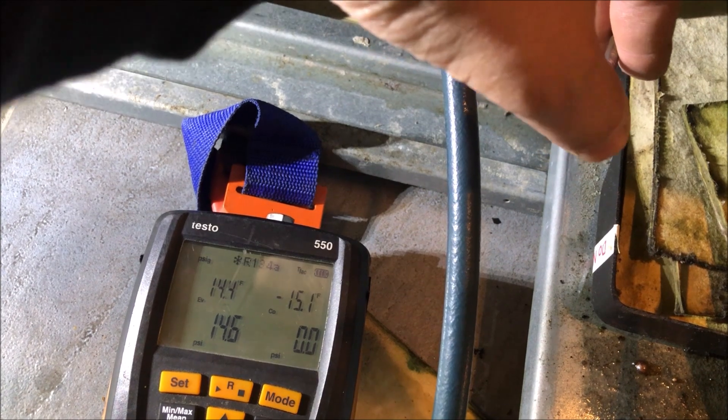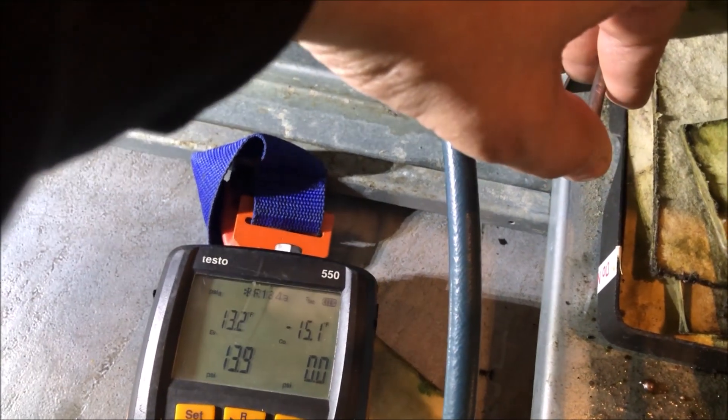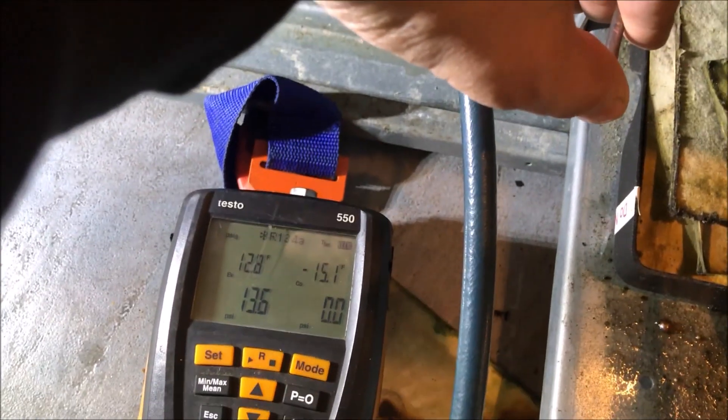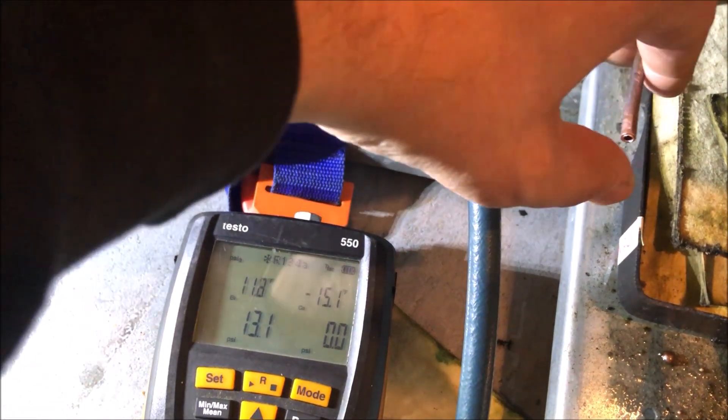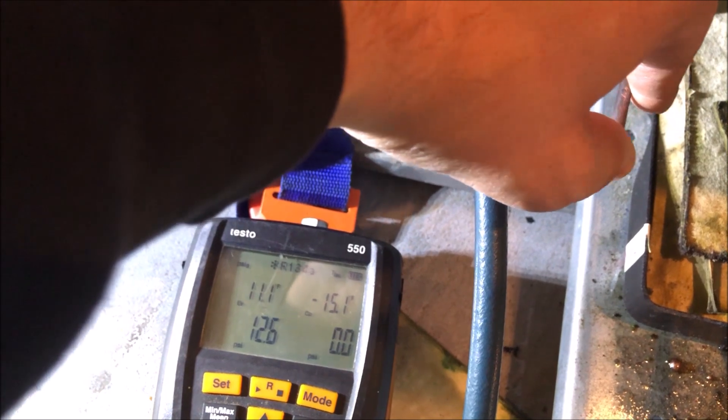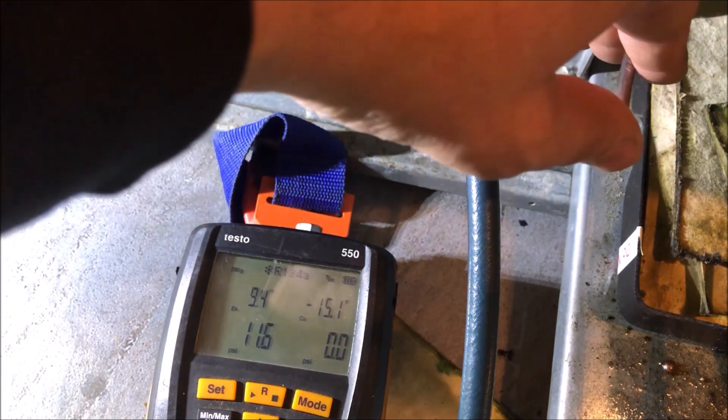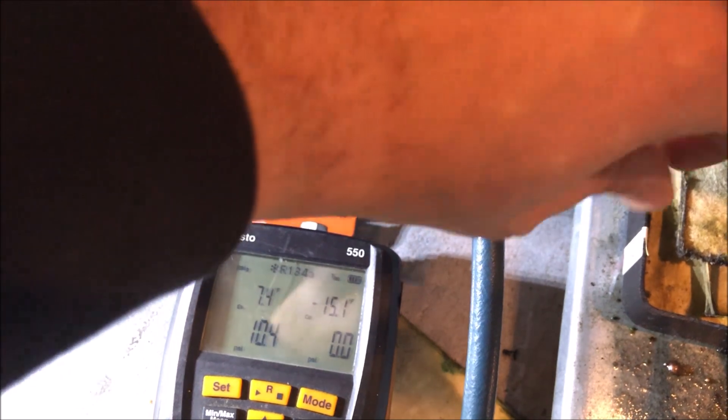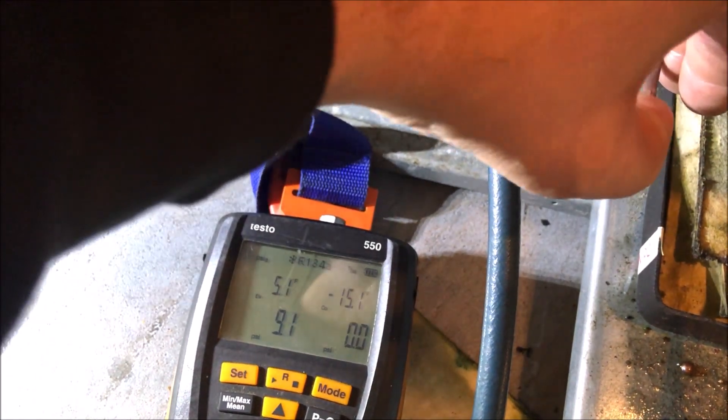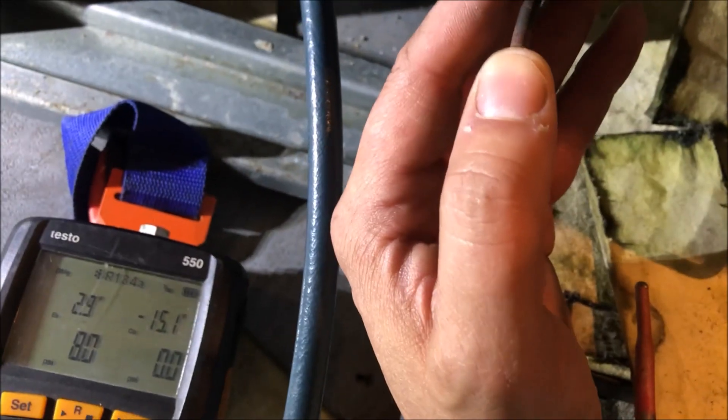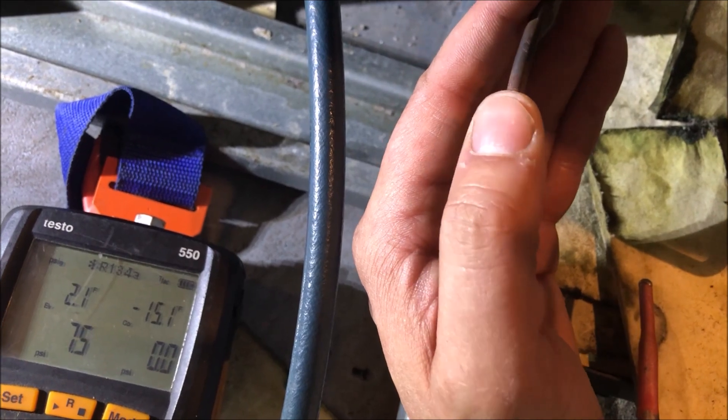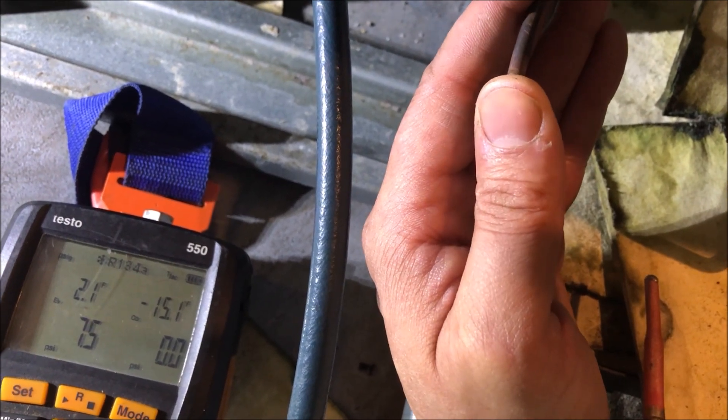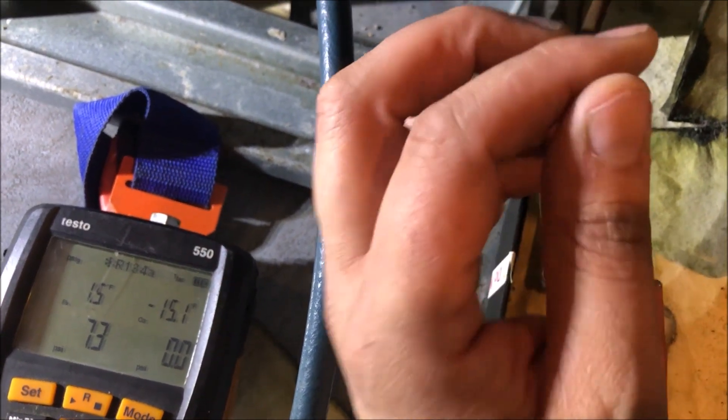So 14 PSI, that's our operating pressures, and look at that, we have really good flow. It is really important that you do this step here because like I said, I've been caught where I'm good at 80 PSI, I didn't check this step, and then obviously we braze everything back together, we vacuum or recharge, we're still in a vacuum, and there's like almost an hour that I've wasted. So I'm actually gonna go even below the 14 PSI. I want to make sure I flow all the way down through. We're still having really good flow. You can hear that's really good flow at these pressures. So that tells me whatever was in here in this system has been pushed out.